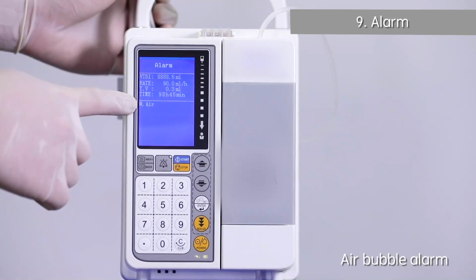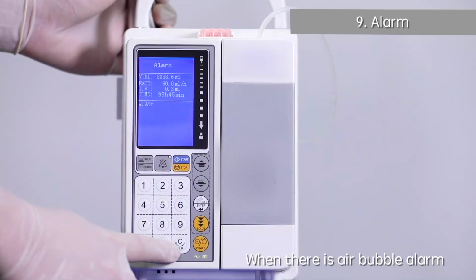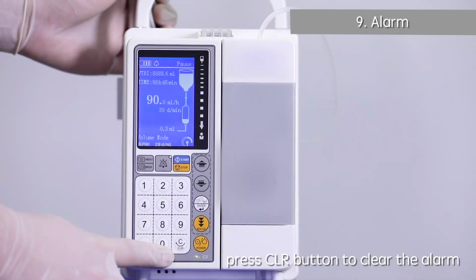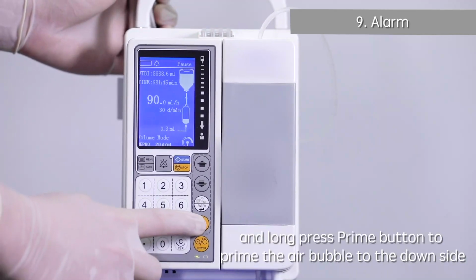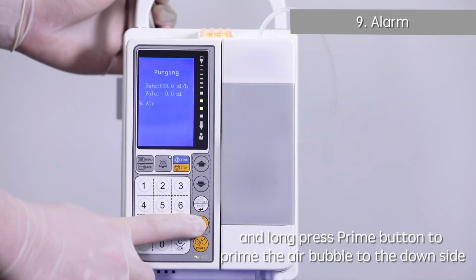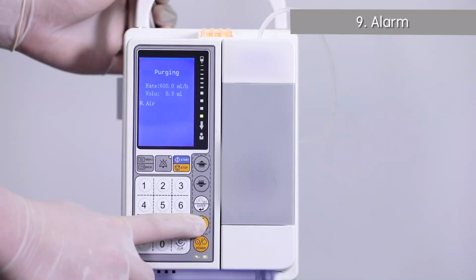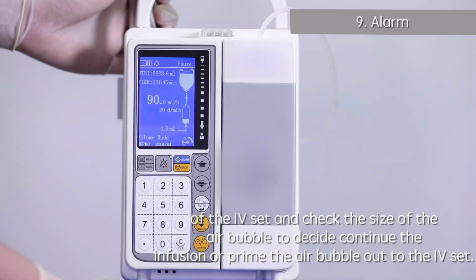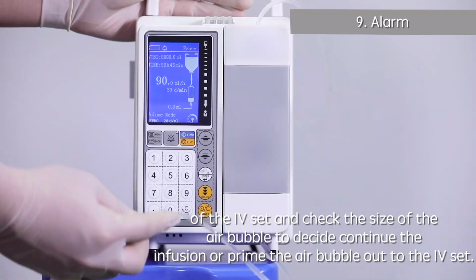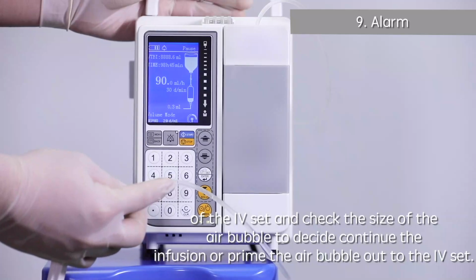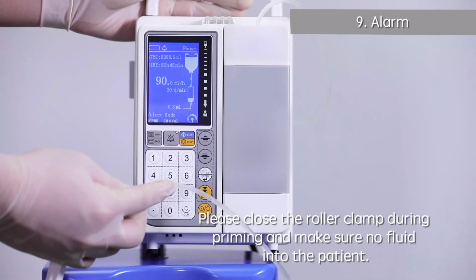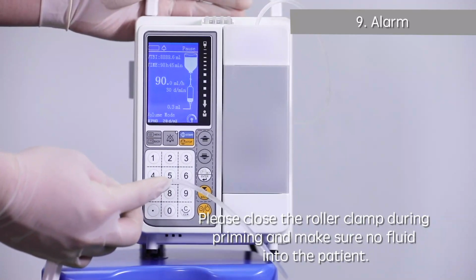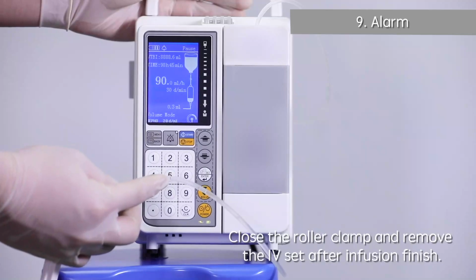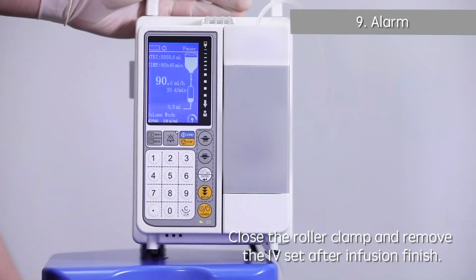1. Air bubble alarm. When there is an air bubble alarm, press the CLR button to clear the alarm, and long press the prime button to prime the air bubble to the downside of the faucet of the IV set, and check the size of the air bubble to decide whether to continue the infusion or prime the air bubble out of the IV set. Please close the roller clamp during priming and make sure no fluid goes into the patient. Close the roller clamp and remove the IV set after infusion finish.